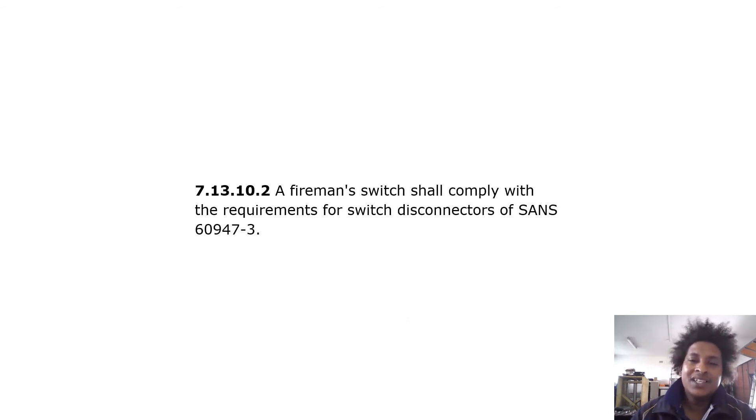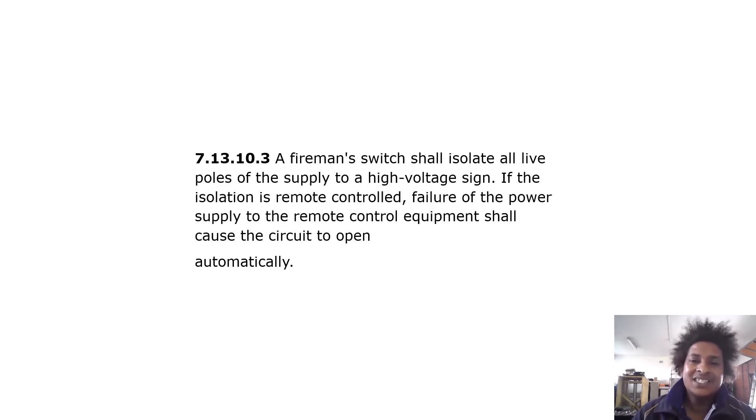A fireman switch shall comply with the requirements for switch disconnectors of SANS 60947-3. It shall isolate all live poles of the supply to a high voltage sign. If the isolation is remote controlled, failure of the power supply to the remote control equipment shall cause the circuit to open automatically.